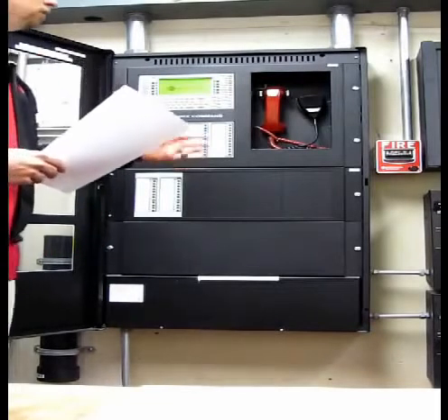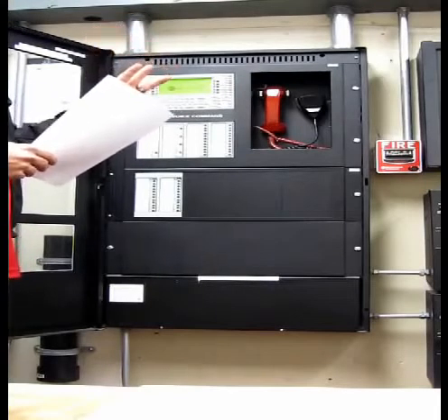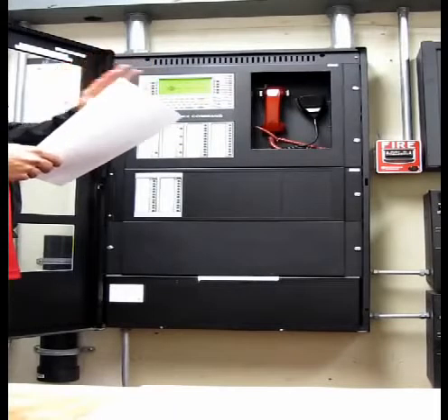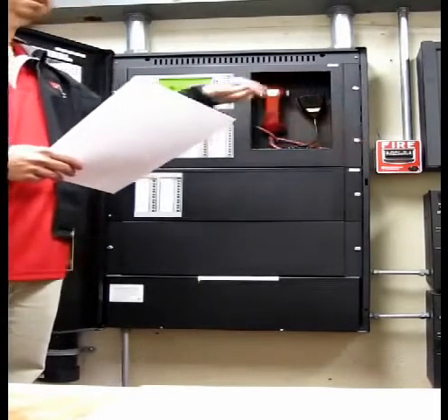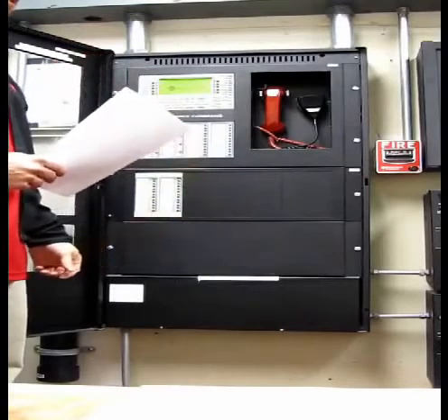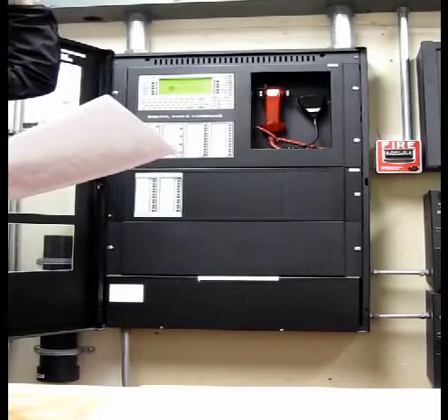Now I did just talk about the sequence of operation on floor of alarm, above and below. The only 3 devices that are different, that are actually full evac, are the 3 pull stations in the building. There's only 3. There's one here, there's one at PBX, and there's one by your guys' main registration desk. So if you pull that, it's going to evacuate all 7 floors. Everything's going to go off at one time.